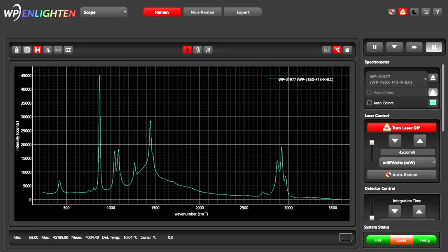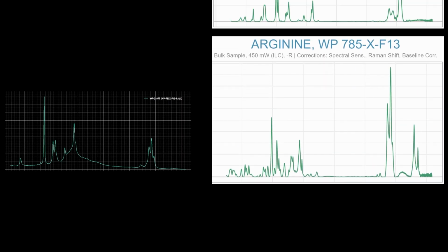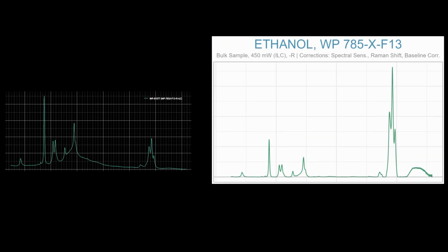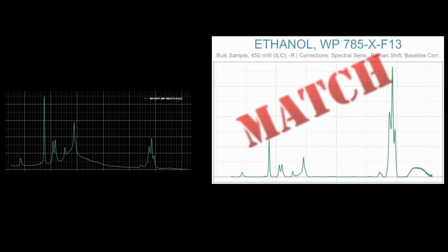But how does this identification really work? I mean, under the hood. Well, I'm glad you asked. Let's find out. The unknown compound is identified by comparing its characteristic Raman spectrum side by side to lots of known reference spectra in a spectral library. If sample and library Raman spectrum are similar, the unknown spectrum is said to be matched. The entire process is therefore called library matching.